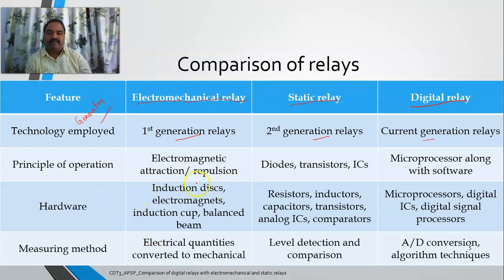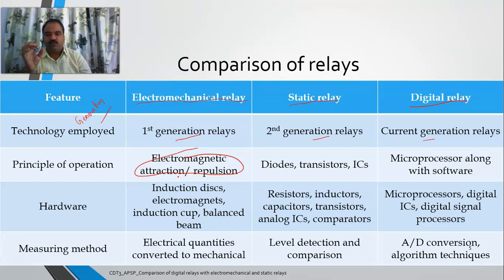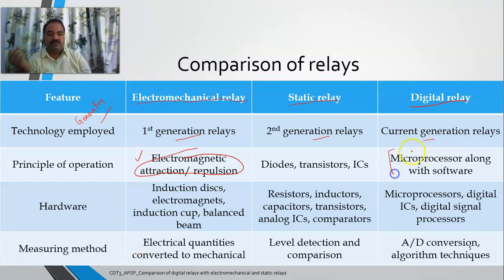Coming to the principle of operation: electromechanical relays use electromagnetic attraction and repulsion. You may have seen many types — balanced beam, attracted armature, induction disc, induction cup relays. The common element is an armature and a magnet, with attraction or repulsion between them. Based on the actuating quantity, movement occurs which gives a signal to the circuit breaker. Static relays use diodes, transistors, and advanced ICs. Digital relays use a microprocessor along with software, employing coding techniques and algorithms — the relay operates based upon the program written.